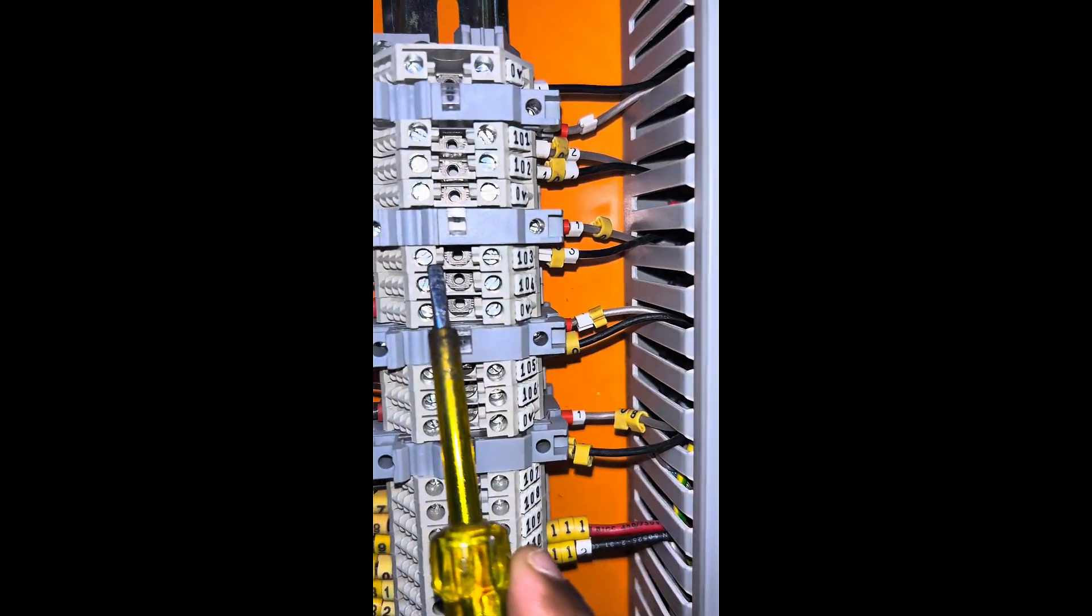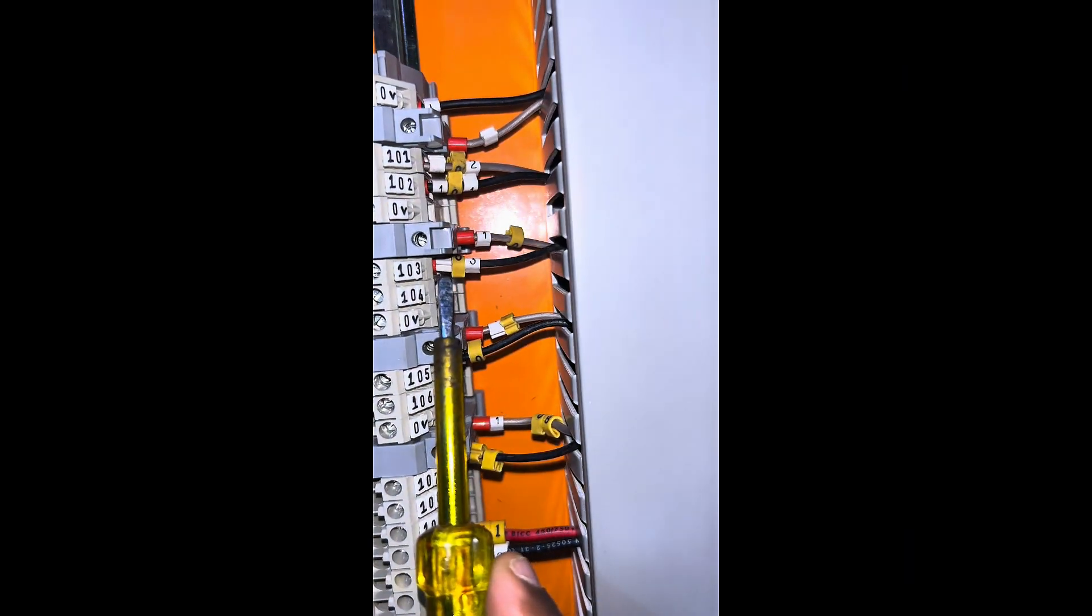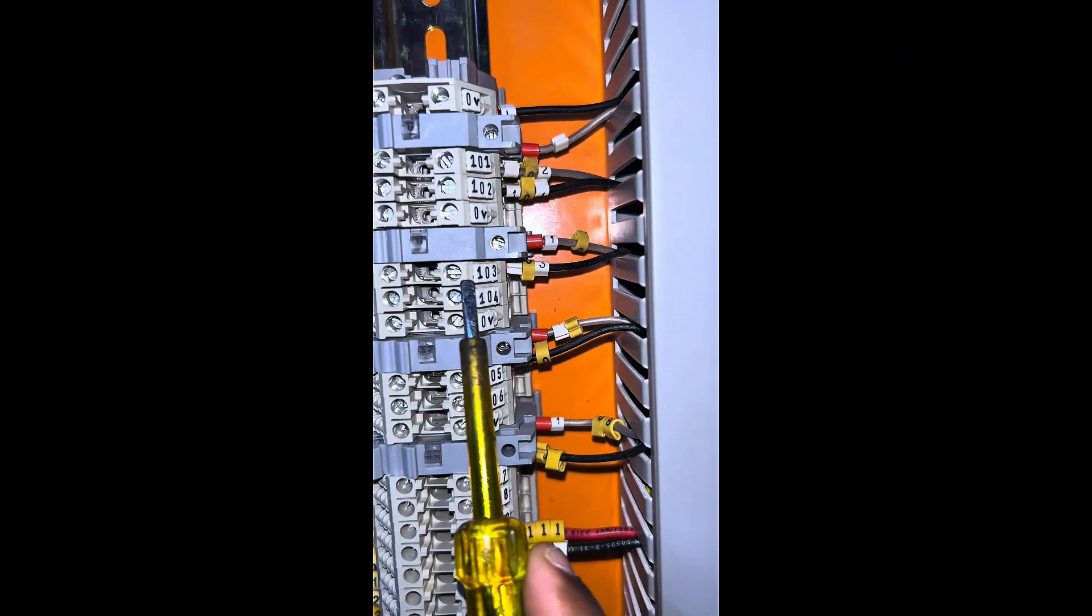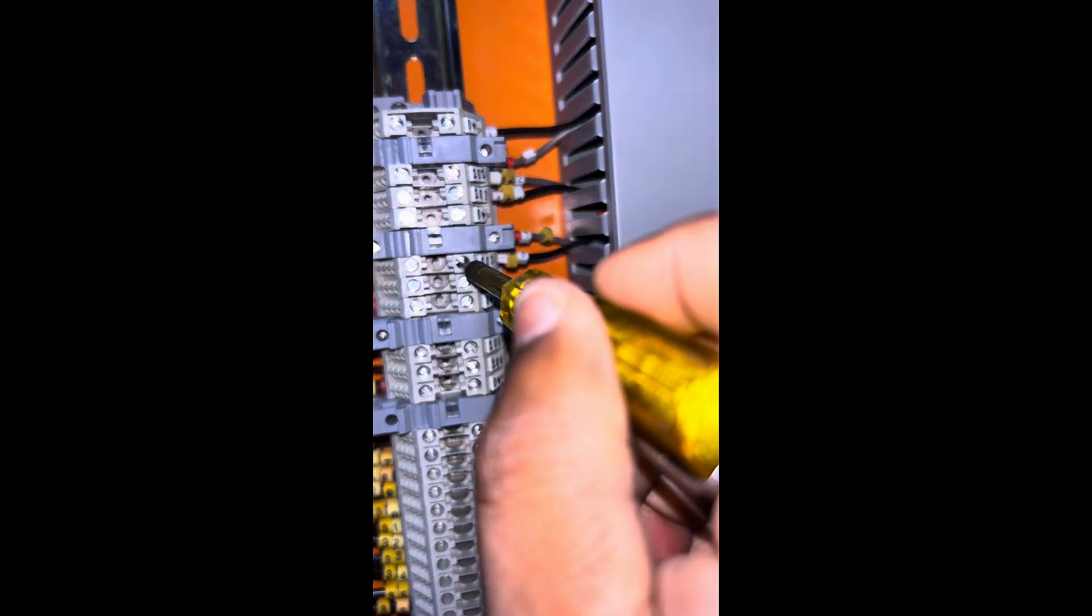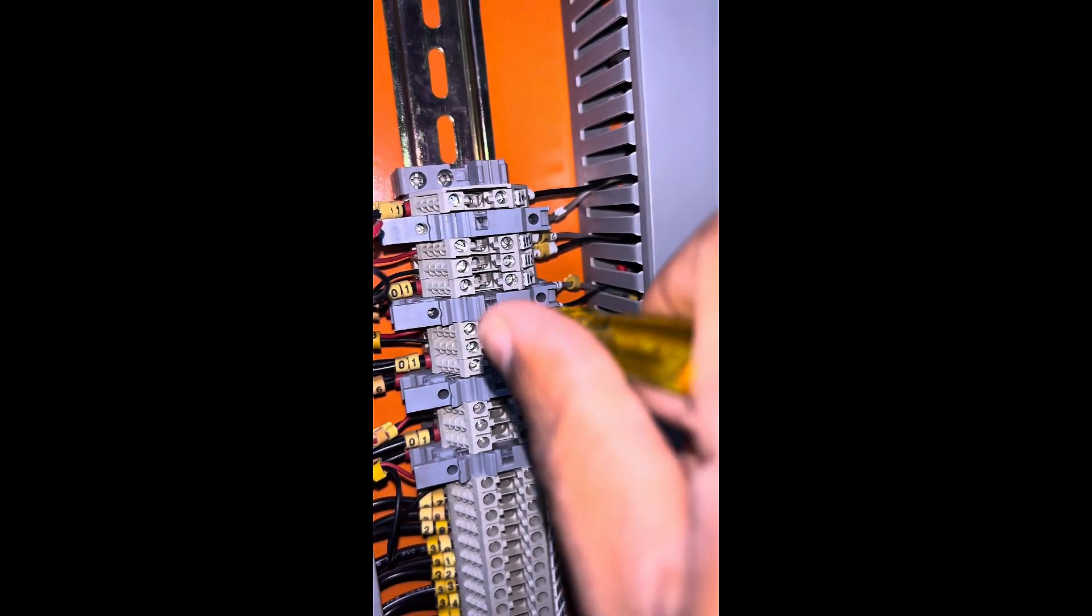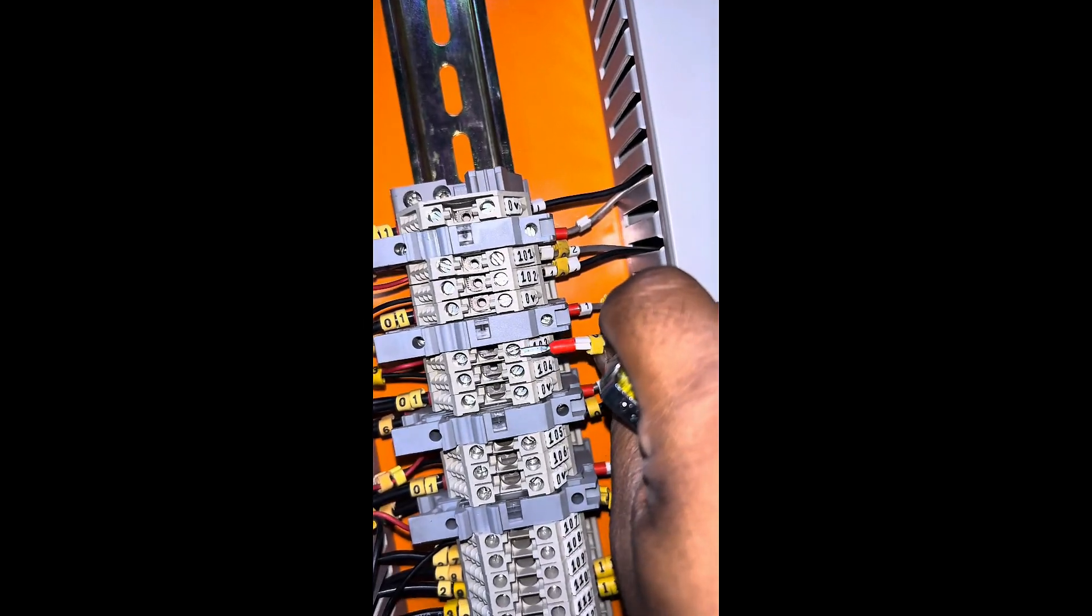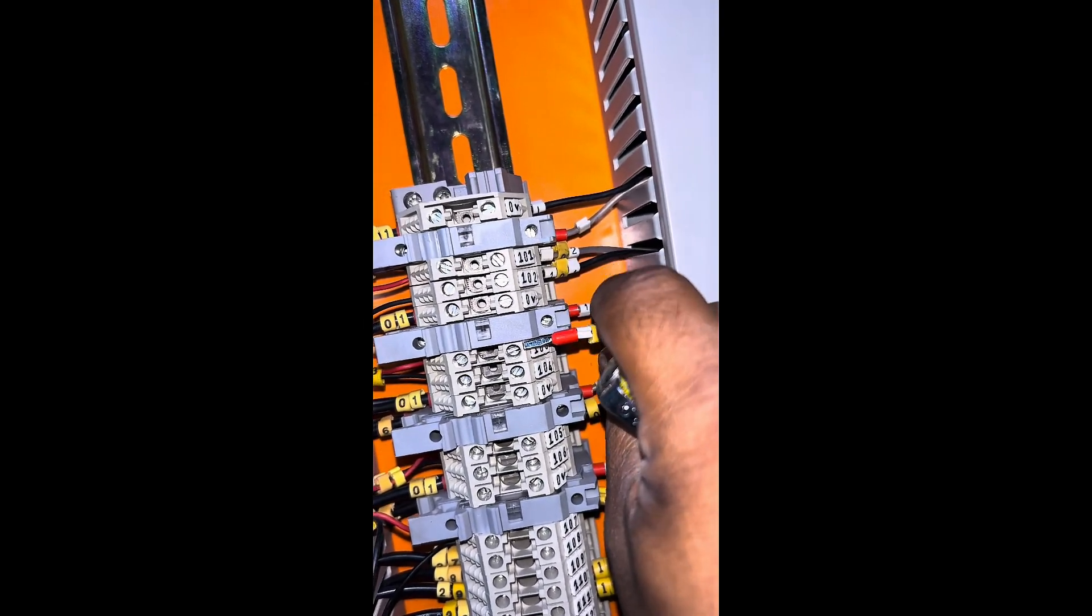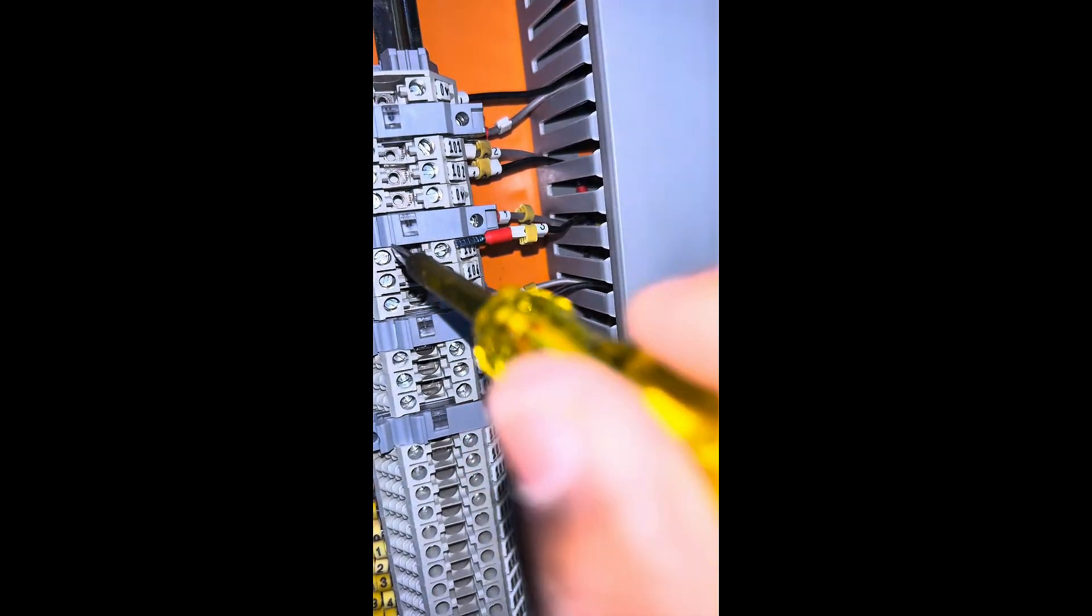In this terminal, this is the return cable where we connected coming back from our water level sensor 2-wire system. So the return cable is connected in that terminal. In order to measure 4-20mA, we need to remove each cable, outgoing section and incoming section of the terminal, so that we can connect the multimeter probes in series.